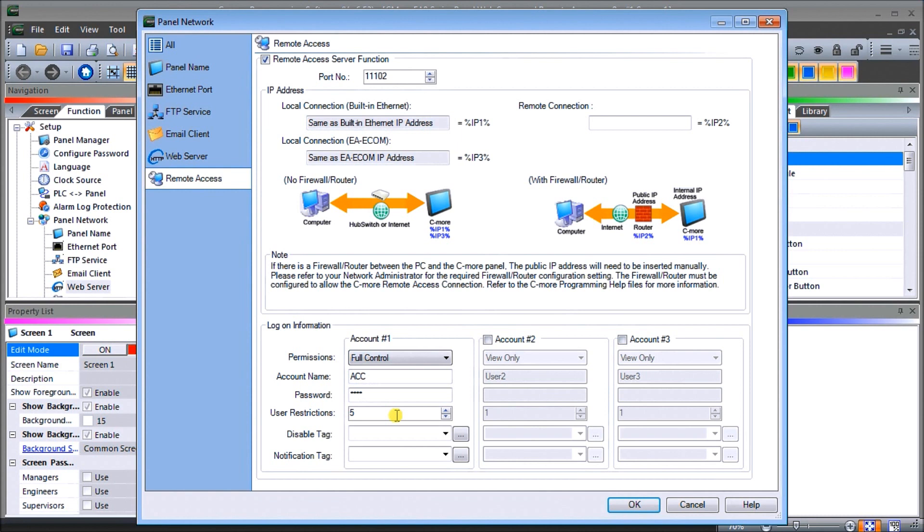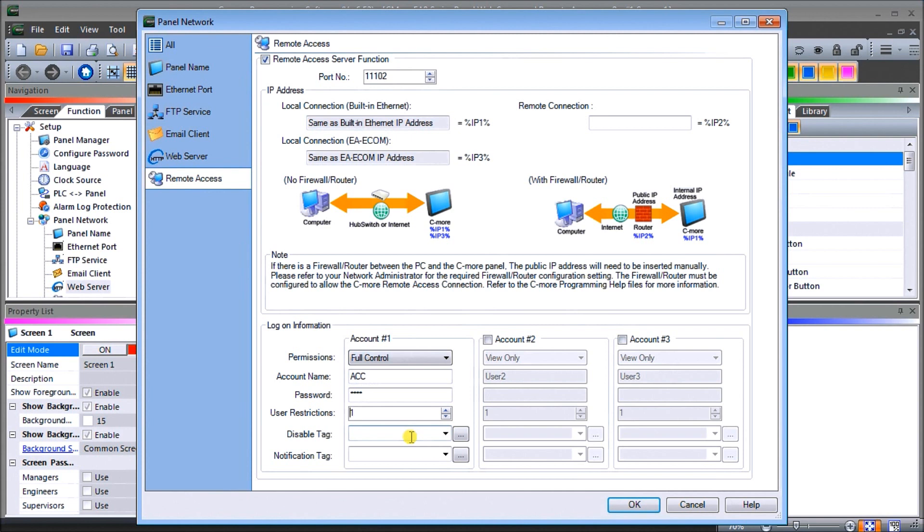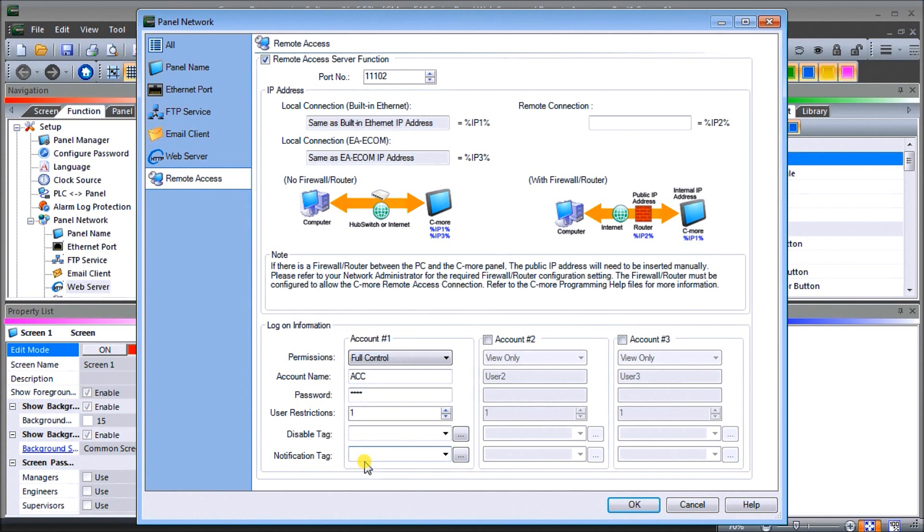We'll turn that back down to one, so only one user. If there's one person operating it and another joins, it'll give an error message to notify that there's someone else using this. We have a disable tag, which allows the PLC program to disable any remote users at any time, so we can have control of when that remote is going to be active. Then we have a notification tag that will indicate through the tag that there's someone connected remotely to the HMI.